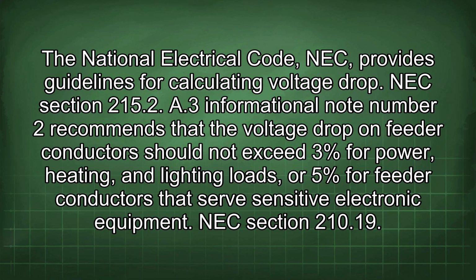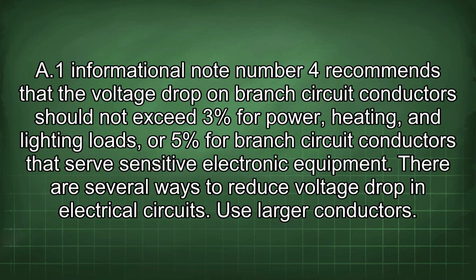The National Electrical Code, NEC, provides guidelines for calculating voltage drop. NEC Section 215.2(A)(3) Informational Note Number 2 recommends that the voltage drop on feeder conductors should not exceed 3% for power, heating, and lighting loads, or 5% for feeder conductors that serve sensitive electronic equipment. NEC Section 210.19(A)(1) Informational Note Number 4 recommends that the voltage drop on branch circuit conductors should not exceed 3% for power, heating, and lighting loads, or 5% for branch circuit conductors that serve sensitive electronic equipment.